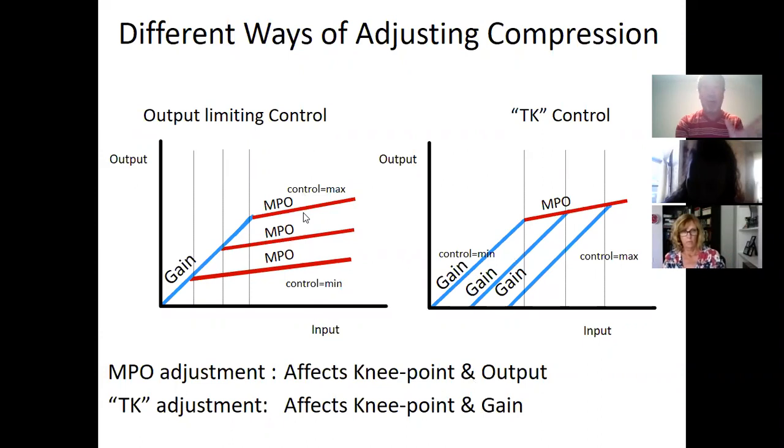Let's pretend this is output limiting compression. Look at how it's got a fairly flat slope. It's really not 2 to 1. Let's pretend it's whatever. You can raise or lower that on the software. I can put it at 115, I can put it at 110, 100, 130, 125. You're going to set it to where you, the clinician, think it should be set.